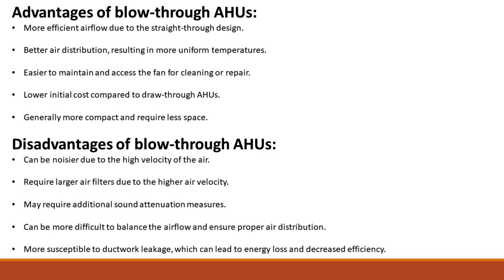Disadvantages of blow-through AHUs: can be noisier due to the high velocity of the air; require larger air filters due to the higher air velocity; may require additional sound attenuation measures; can be more difficult to balance the airflow and ensure proper air distribution; and more susceptible to ductwork leakage, which can lead to energy loss and decreased efficiency.